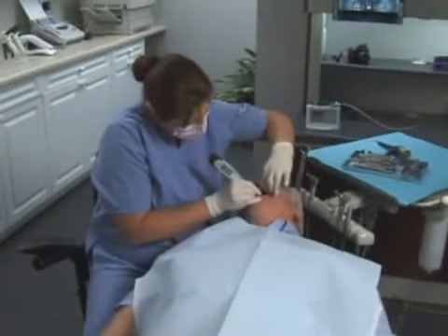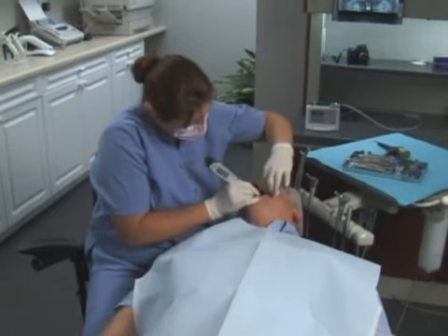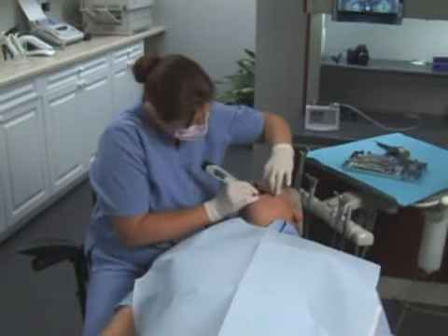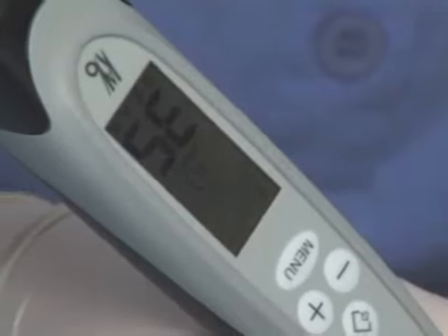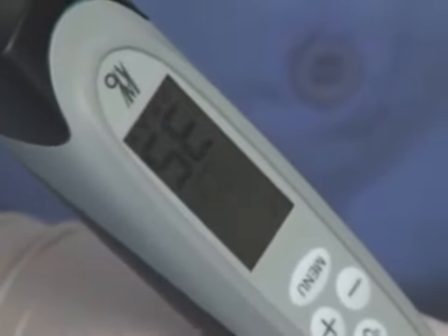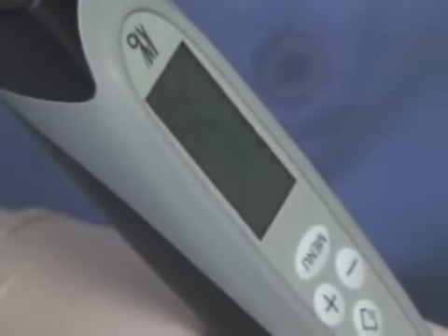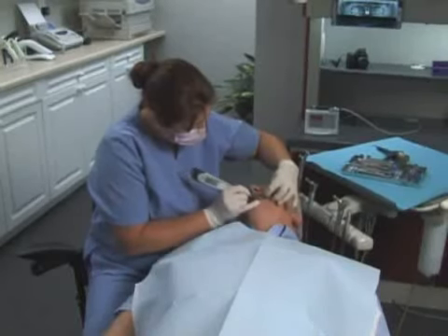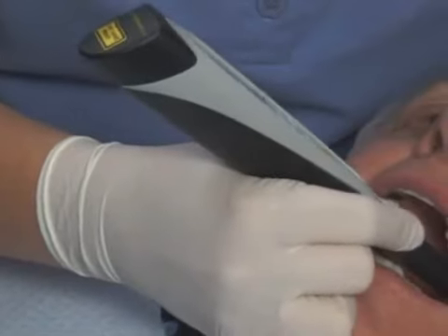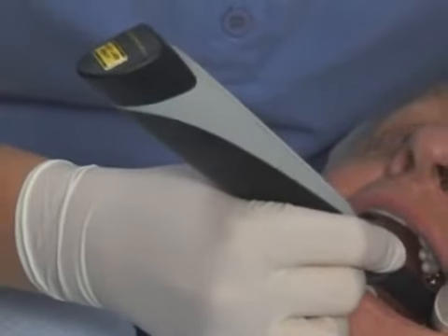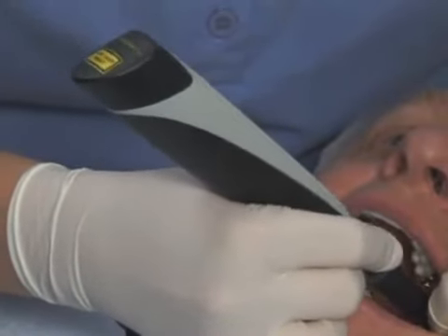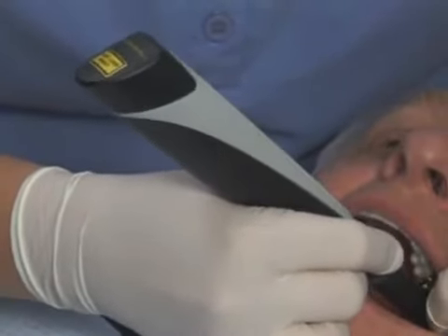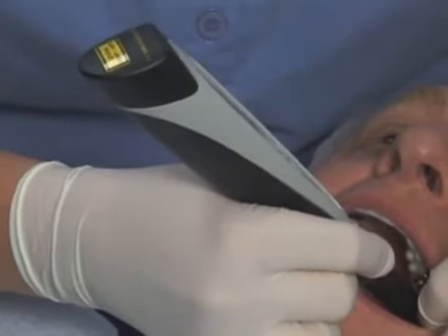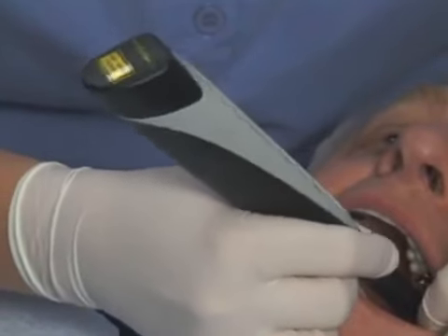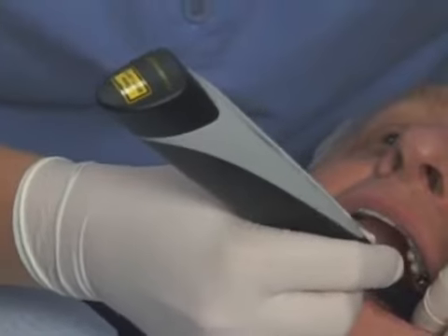Scan tooth surfaces with light contact while monitoring the audio signal. Listen for an increase in tone pitch, which alerts you to observe the display to pinpoint the exact site on the tooth surface that corresponds to the elevated values. In fissure areas, the tip must be slowly rocked in a pendulous motion to carefully gather data from each pit and groove at various angles. Do not apply too much pressure on the laser tip, but do make contact with the tooth surface.